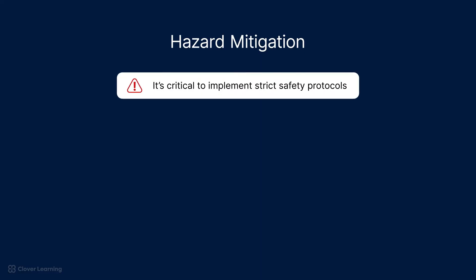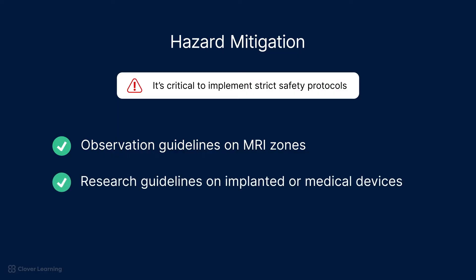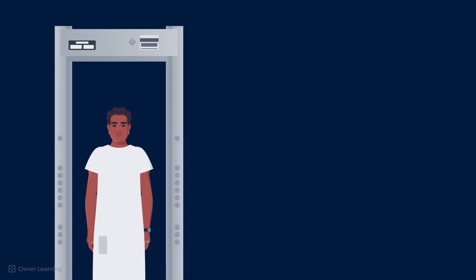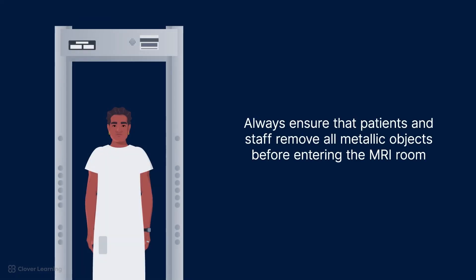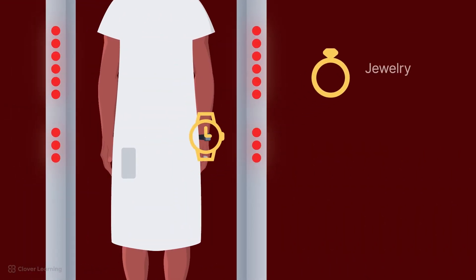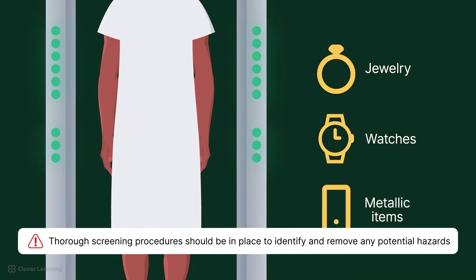To mitigate projectile hazards, it's critical to implement strict safety protocols, like observation guidelines on MRI zones and research guidelines on implanted or medical devices. Additionally, technologists should always ensure that patients and staff remove all metallic objects before entering the MRI room. This includes jewelry, watches, and any metallic items in pockets. Thorough screening procedures should be in place to identify and remove any potential hazards.